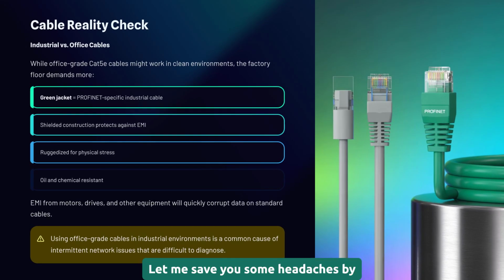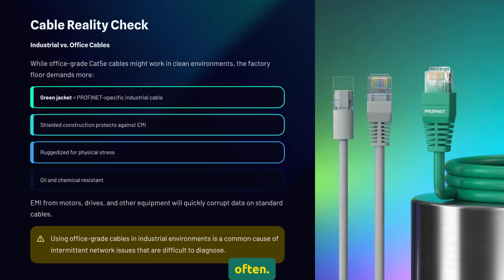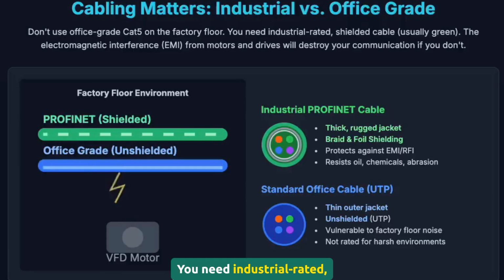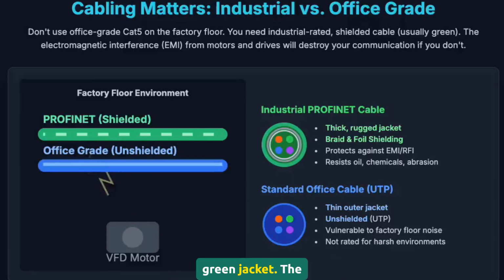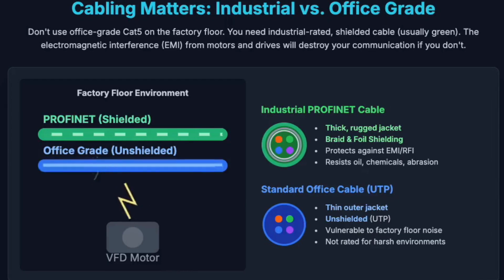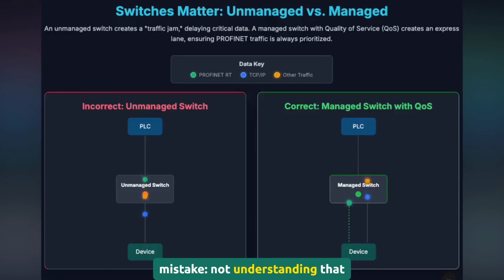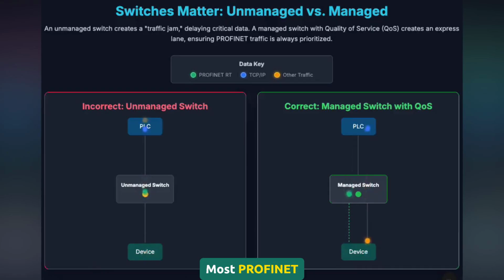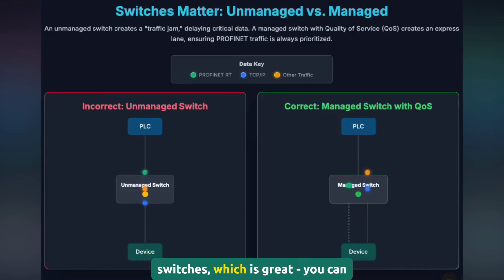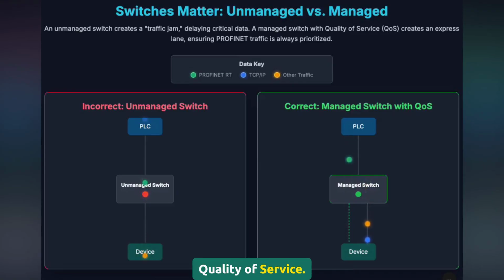Let me save you some headaches by covering the mistakes I see most often. First, cabling. Yes, PROFINET uses Ethernet, but for the love of all that's holy, don't use office-grade Cat5 cable on the factory floor. You need industrial-rated shielded cable, usually with a green jacket. The EMI from motors and drives will absolutely destroy your communication if you don't. Second mistake, not understanding that switches matter. Most PROFINET devices have built-in switches, which is great, you can daisy chain them. But if you're using external switches, make sure they're managed switches that support quality of service.